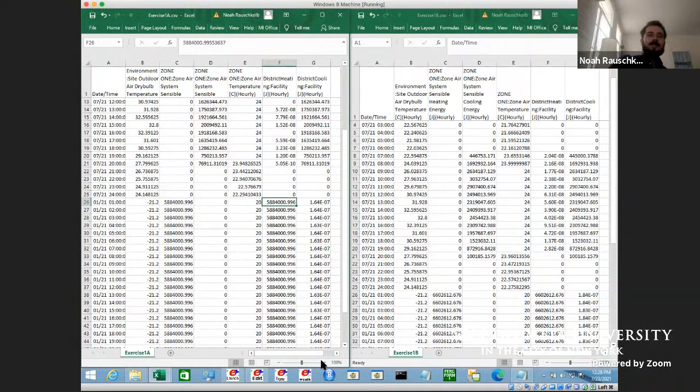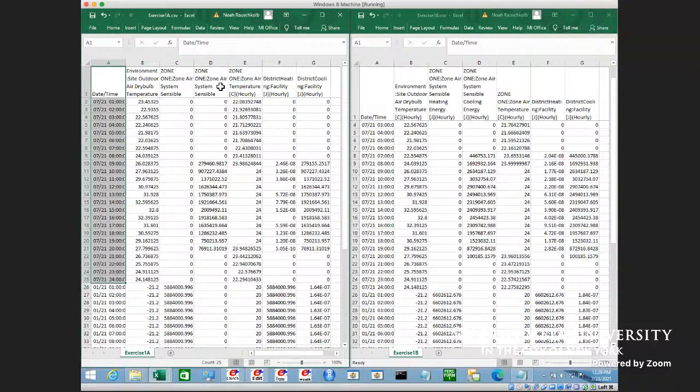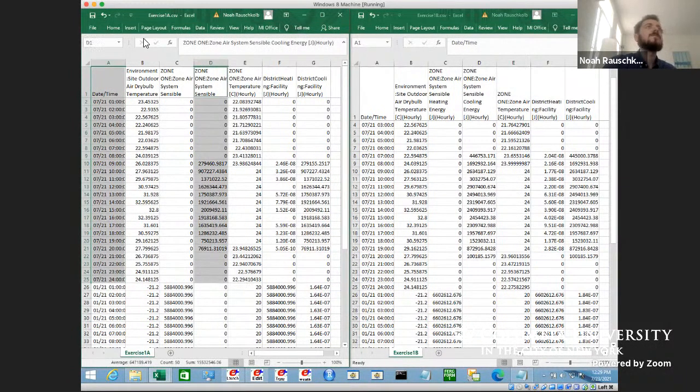Yeah. So you can see very clearly how it changes the output for the winter design day. It's going to be very subtle and interesting if we actually plotted all this data, because I made this window in mine east facing, you're going to get an earlier peak. Let's see if we can plot our summer day, zone air. July 21.